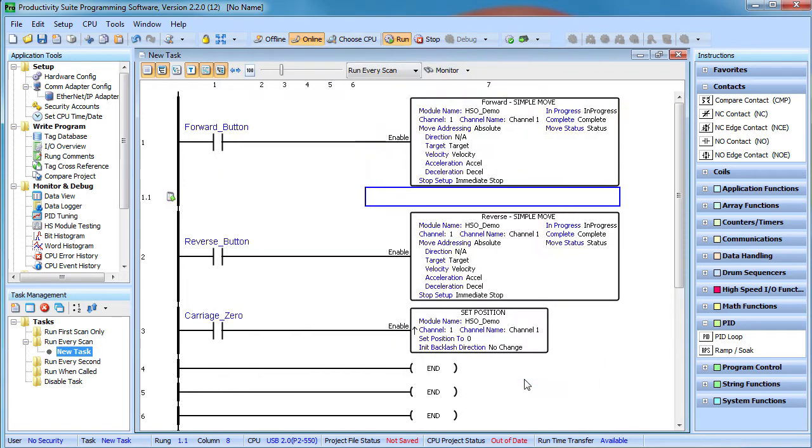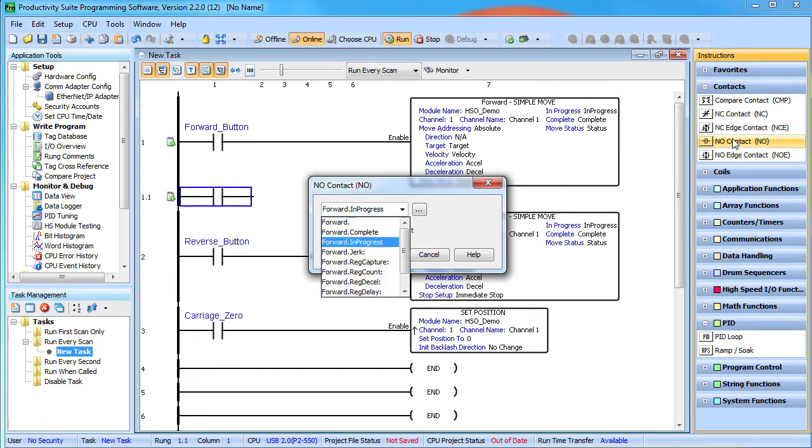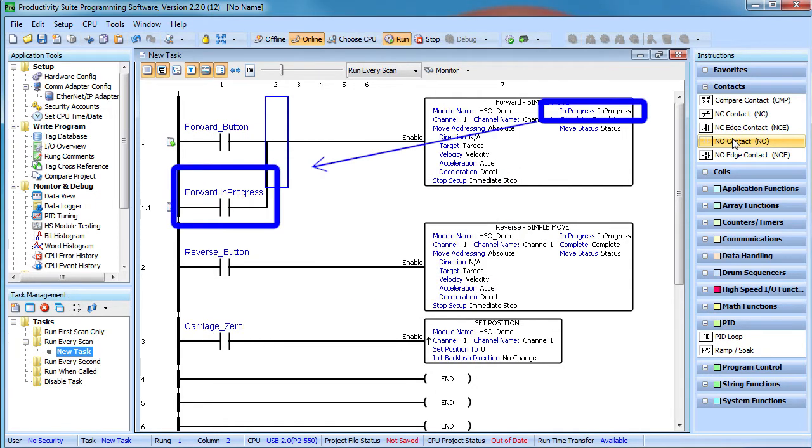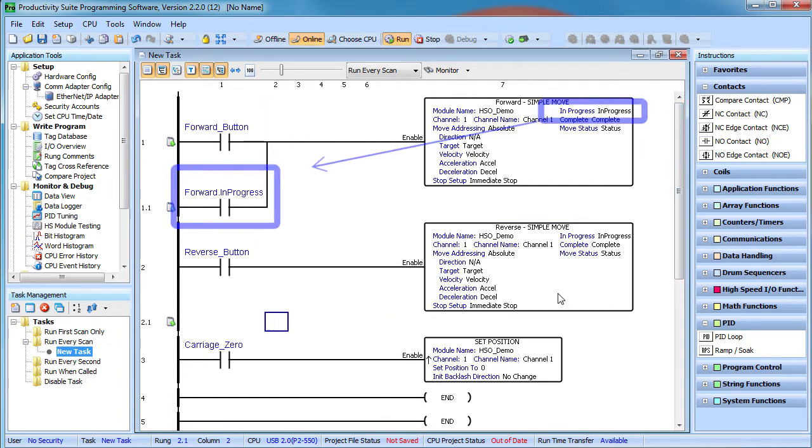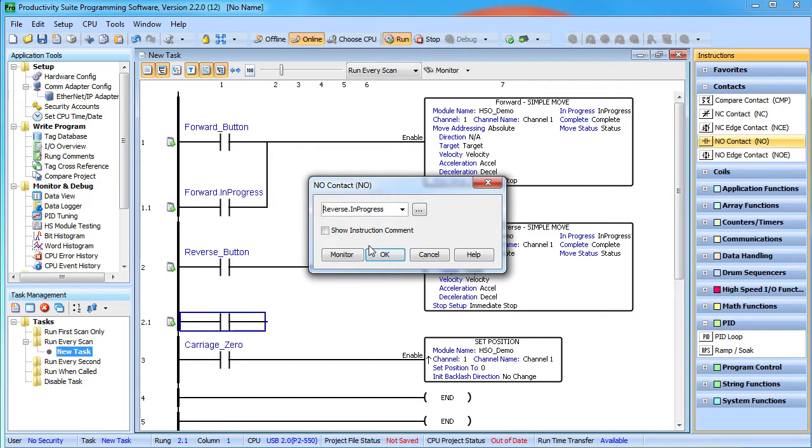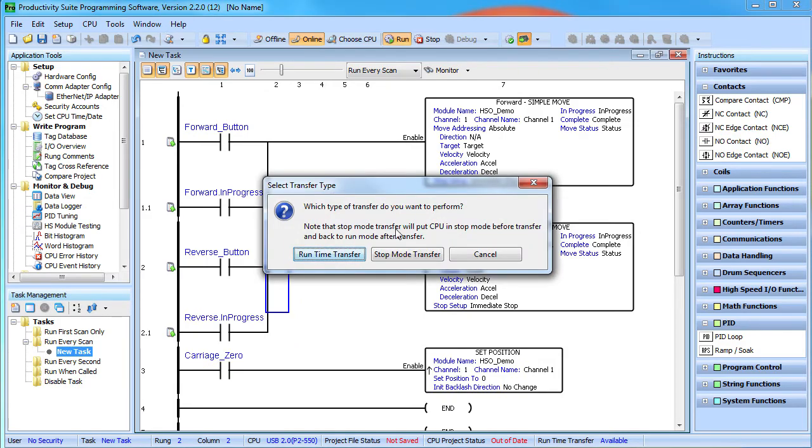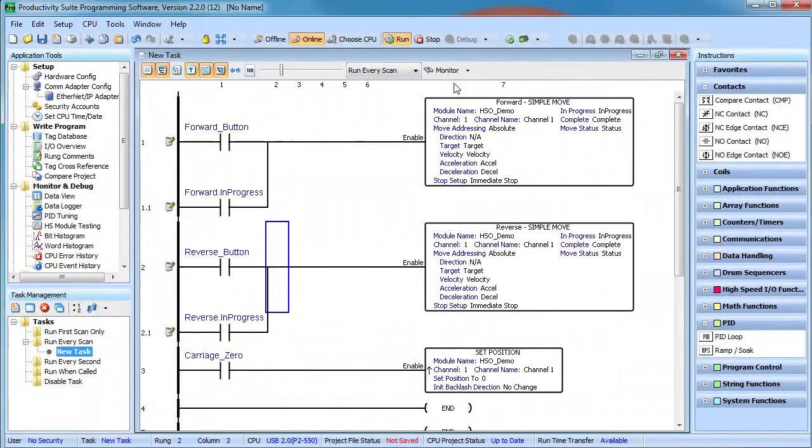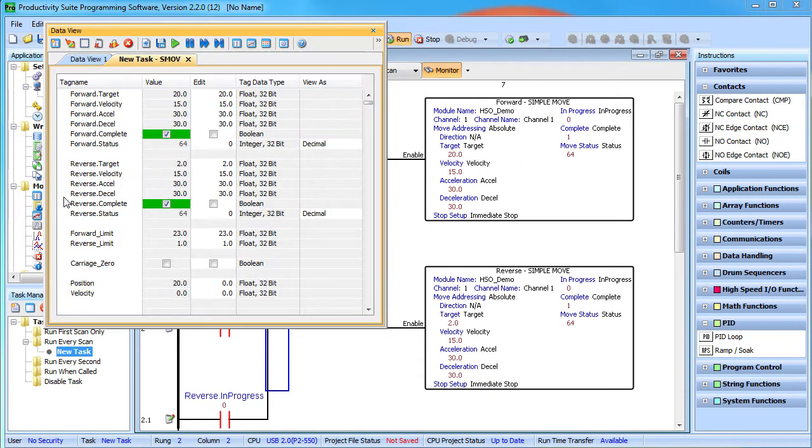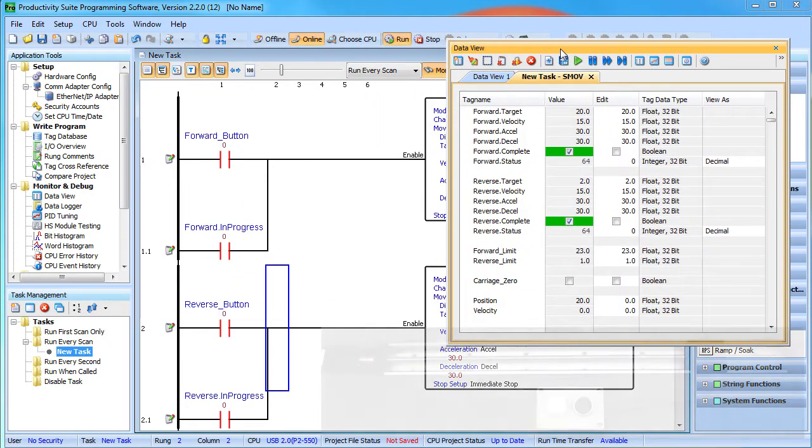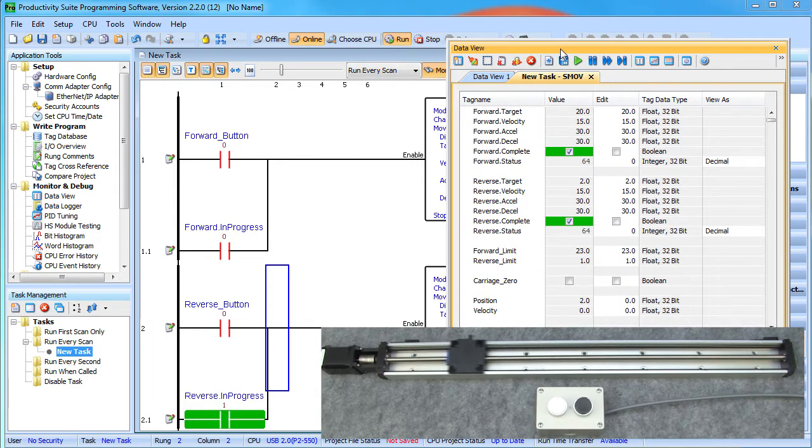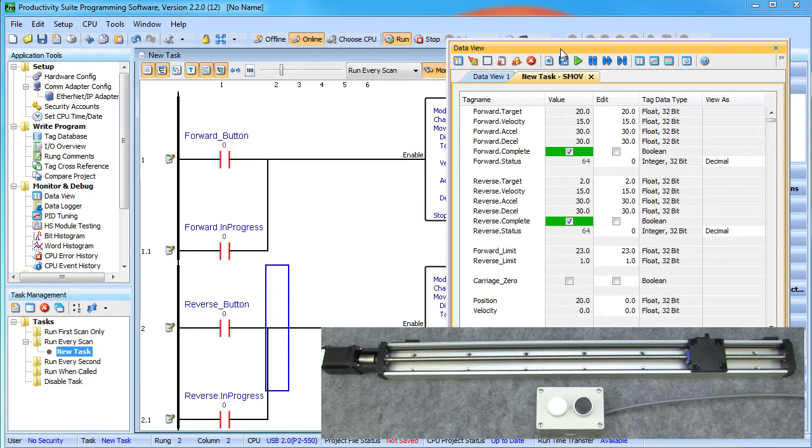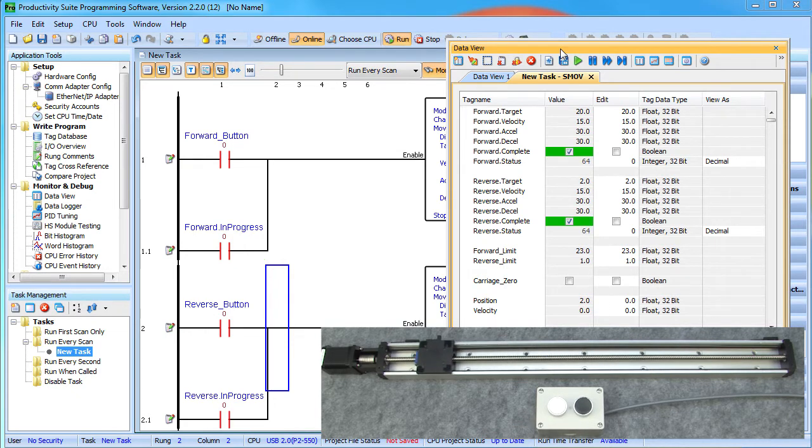Now I don't like holding the button down, so let's seal this contact with an in progress bit. Now the button will start the command, but the in progress bit will keep it running. We call that sealing a contact. Let's do the same thing for the reverse direction and send that down to the controller. Let's turn on monitoring so we can see the status of the contacts. Notice that we don't need to update the tags because we did a run time transfer and sure enough, if I temporarily push the button, that contact turns on and back off but the in progress bit keeps the command running to completion – perfect.